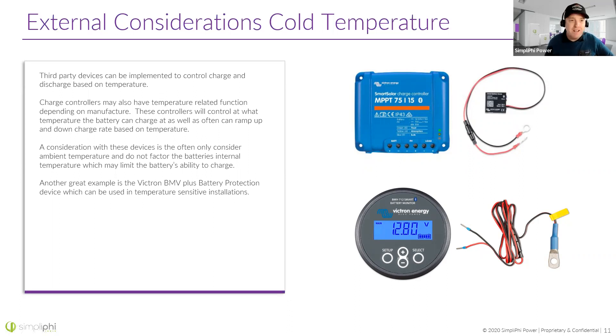If you don't use our built-in thermostatic heating thermostats, you can use third-party designs. Victron makes a lot of great products — one is the BMV 712, a battery monitor that can also be used to curtail charge rates from a charge controller, preventing charging being pushed into a battery below freezing temperature. Again, try to sandwich that little sensor between batteries to measure internal temperature.